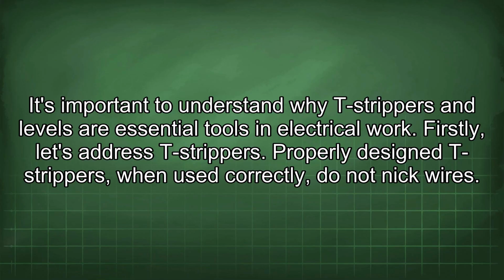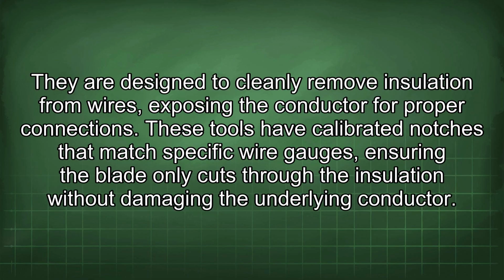It's important to understand why T-strippers and levels are essential tools in electrical work. Firstly, let's address T-strippers. Properly designed T-strippers, when used correctly, do not nick wires. They are designed to cleanly remove insulation from wires, exposing the conductor for proper connections.